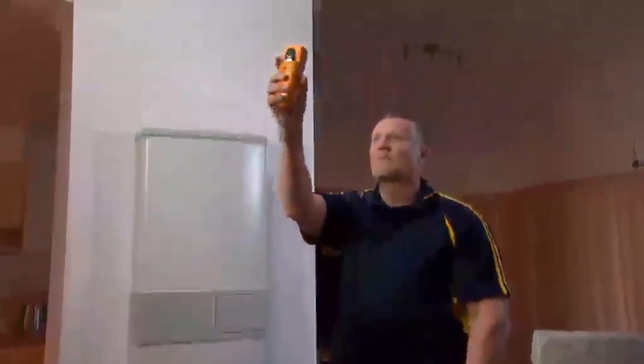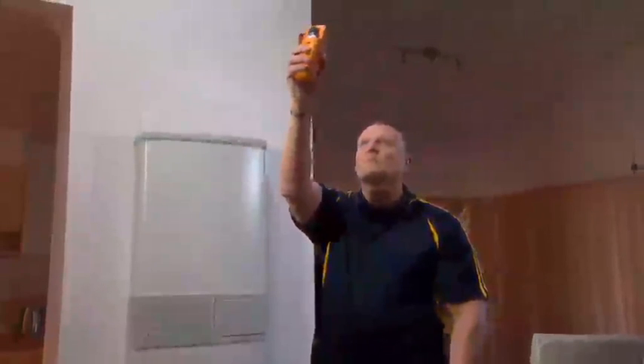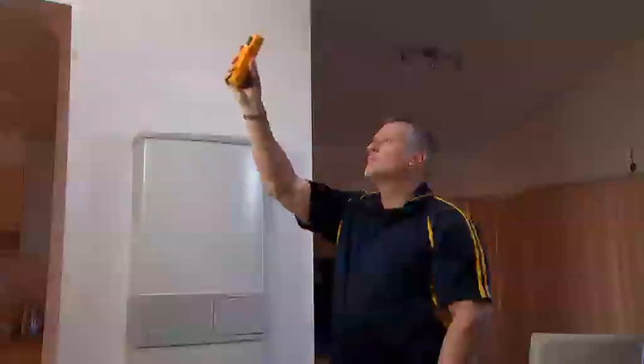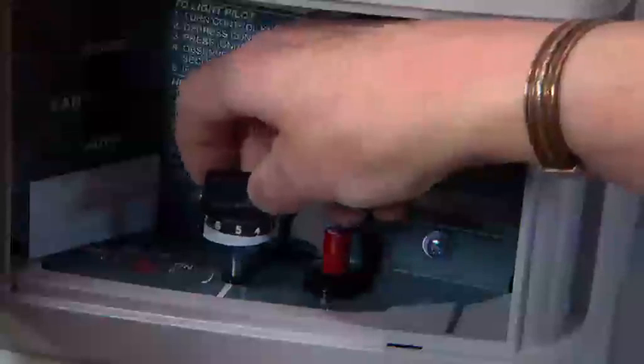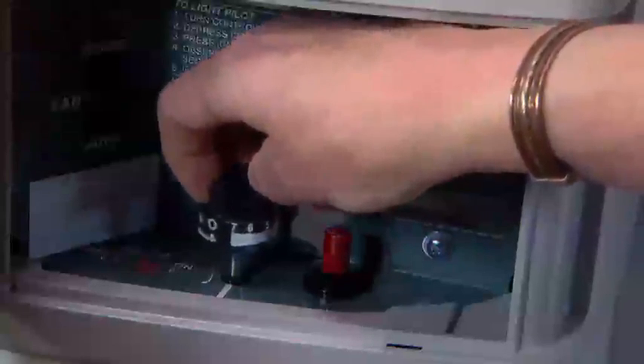Especially look for sooting at the flue cowl, as this may indicate the gas appliance has not been operating properly. Turn on your detection equipment and take a background reading in separate locations within the building, as the problem may be caused by a separate source and not the gas appliance. Light the gas and operate with the burner and fan, if fitted, on the higher setting, and check the flame where possible. With the exception of decorative log fires, a blue flame is considered to be an indication of normal operation for the gas heater.